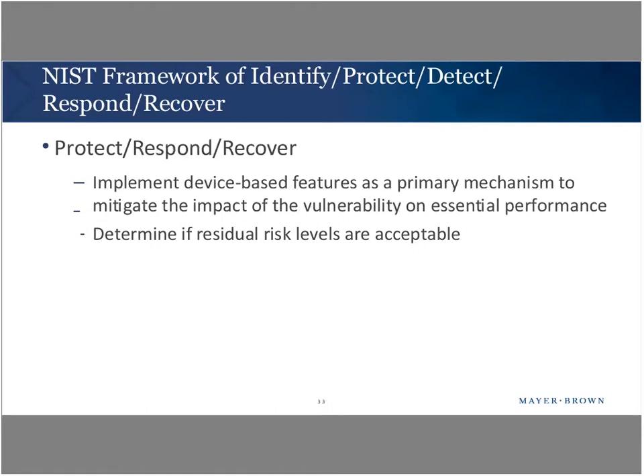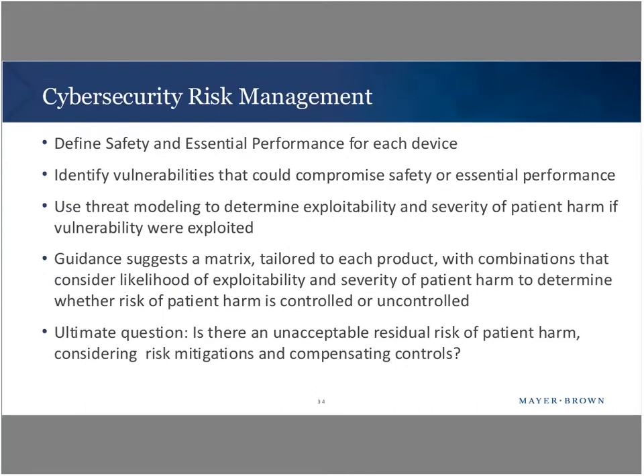And then this is basically what FDA requires. You have to define safety and essential performance for each device. Then, based on those definitions, identify the vulnerabilities that could compromise either of those things. And then use threat modeling to determine how a cyber attacker might exploit those and what severity of patient harm there might be if they were to do so. The guidance document suggests the matrix, although it acknowledges that you could come to these conclusions in other manners. But it basically wants you to look at a combination of exploitability versus the severity of the patient harm to determine whether the risk of patient harm is controlled or uncontrolled. And those two terms will essentially control your reporting requirements. So the ultimate question is: is there an unacceptable residual risk of patient harm considering the risk mitigations and compensating controls?